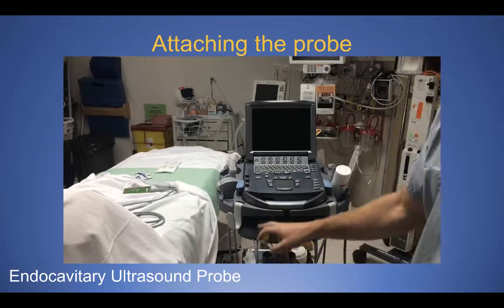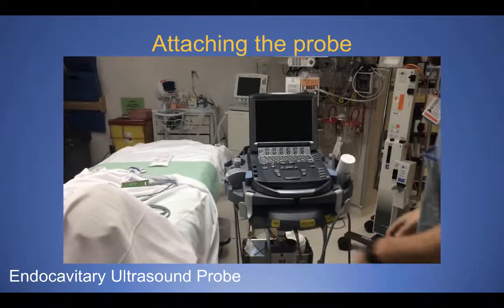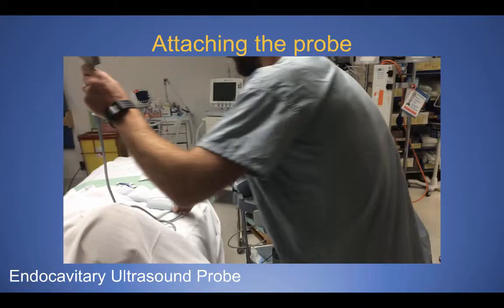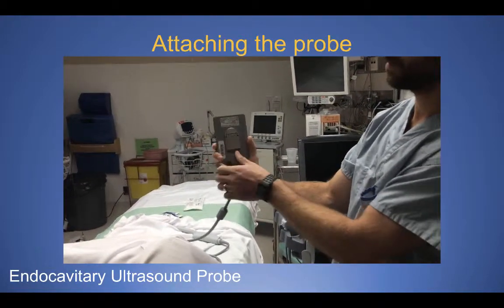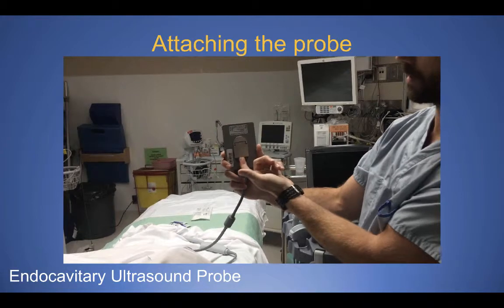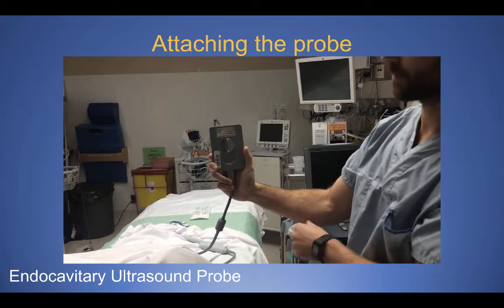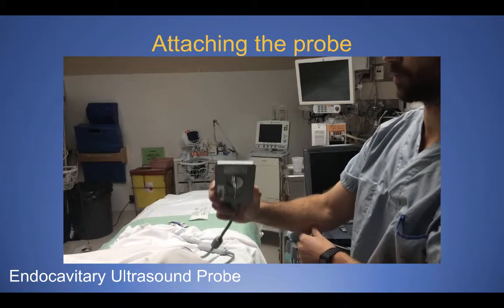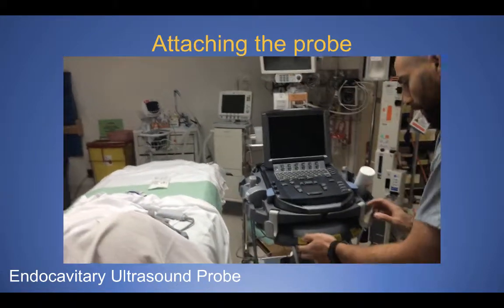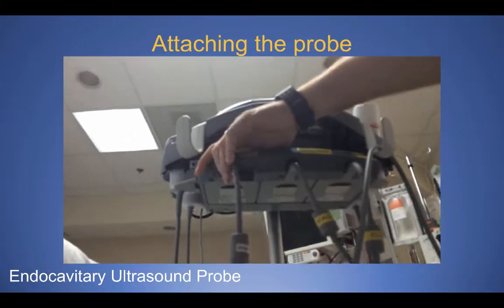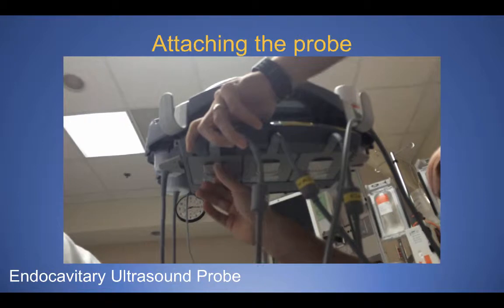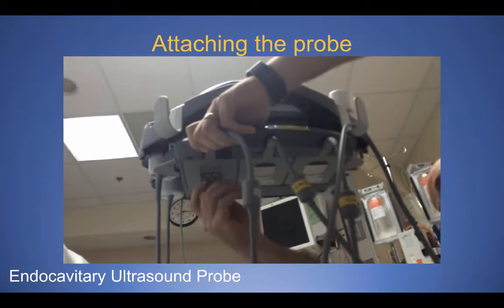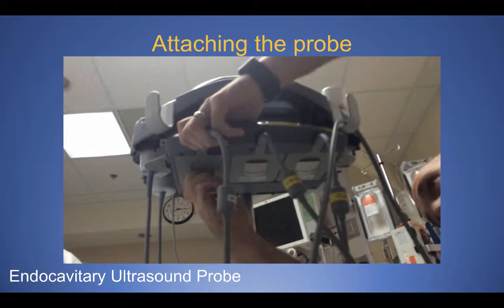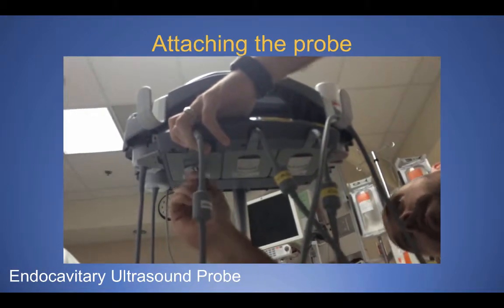Once this is done, you need to choose which probe you're going to take off. Each of these probes has a locking mechanism that you can see here. So that's in the locked position. If you want to unlock it, you flip the latch up, rotate it 90 degrees, and then that'll disengage it and you can pull the probe out. If you come down here, you can see how we have our probes here. I'm going to take off the fast probe. So I flip it down, rotate 90 degrees maybe. There we go. Comes off.